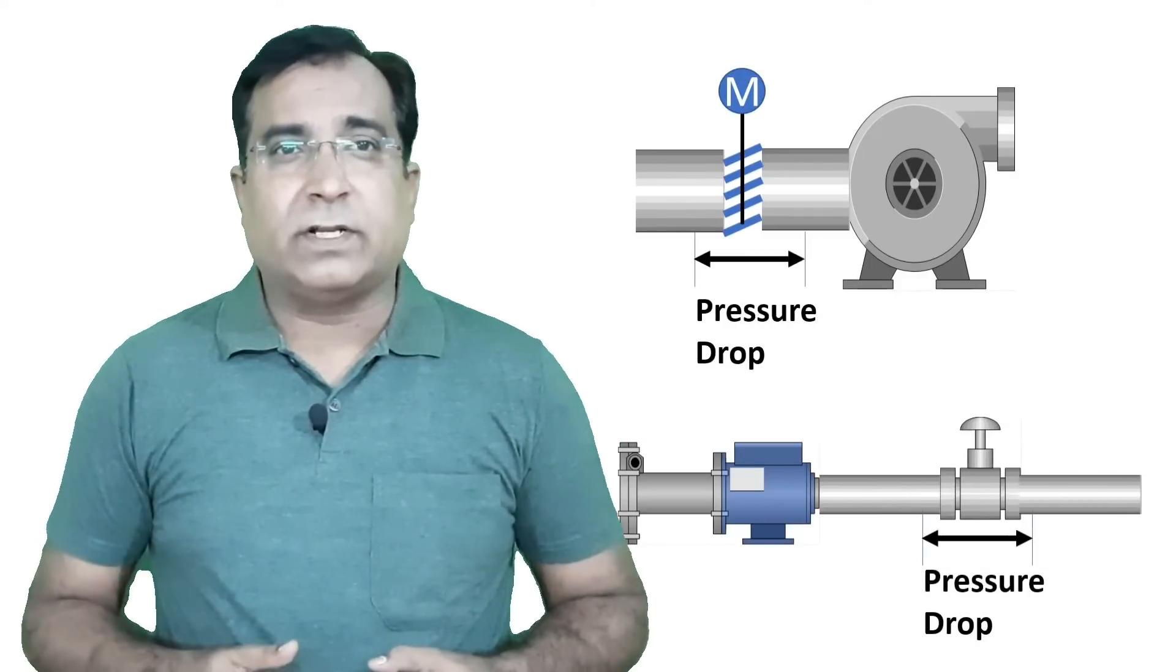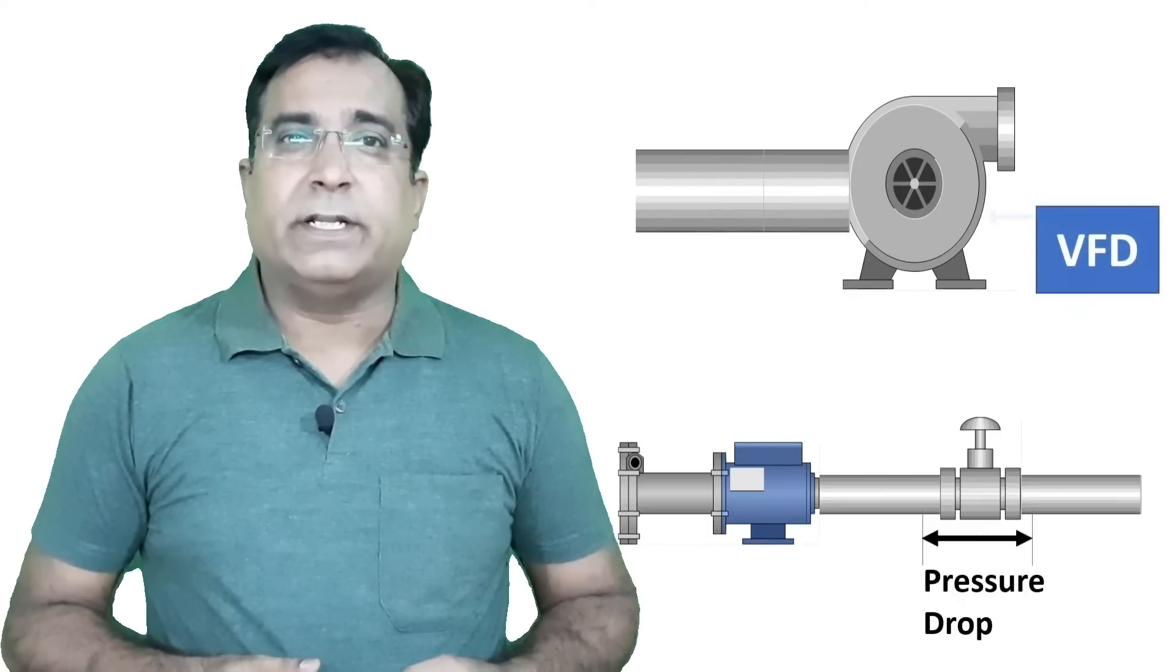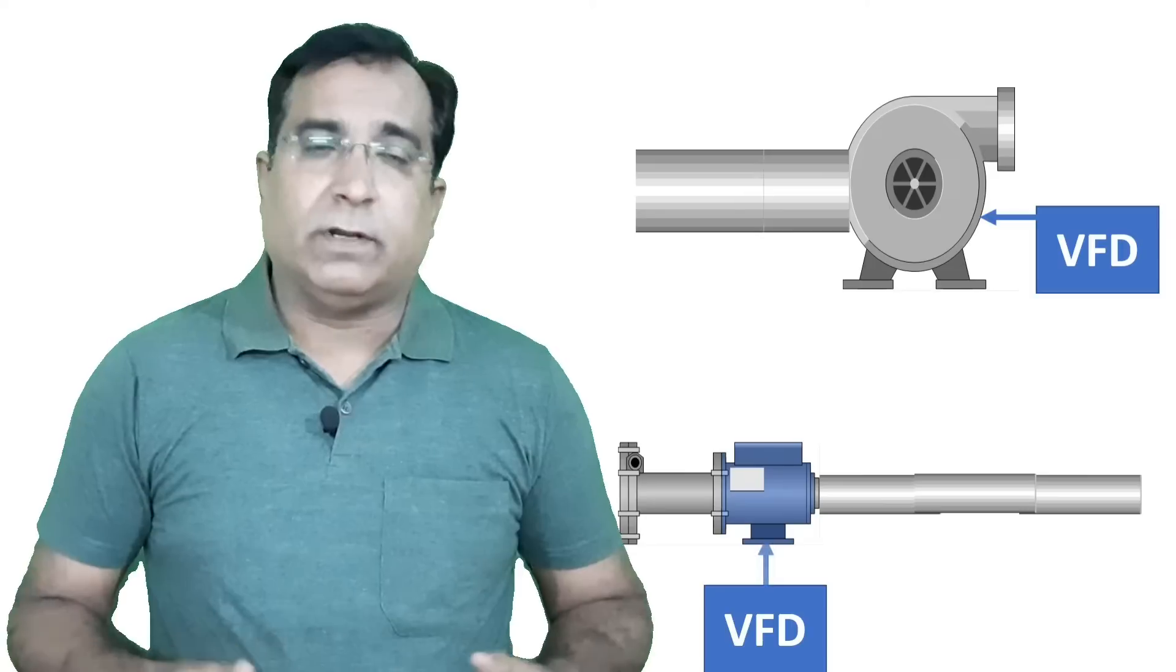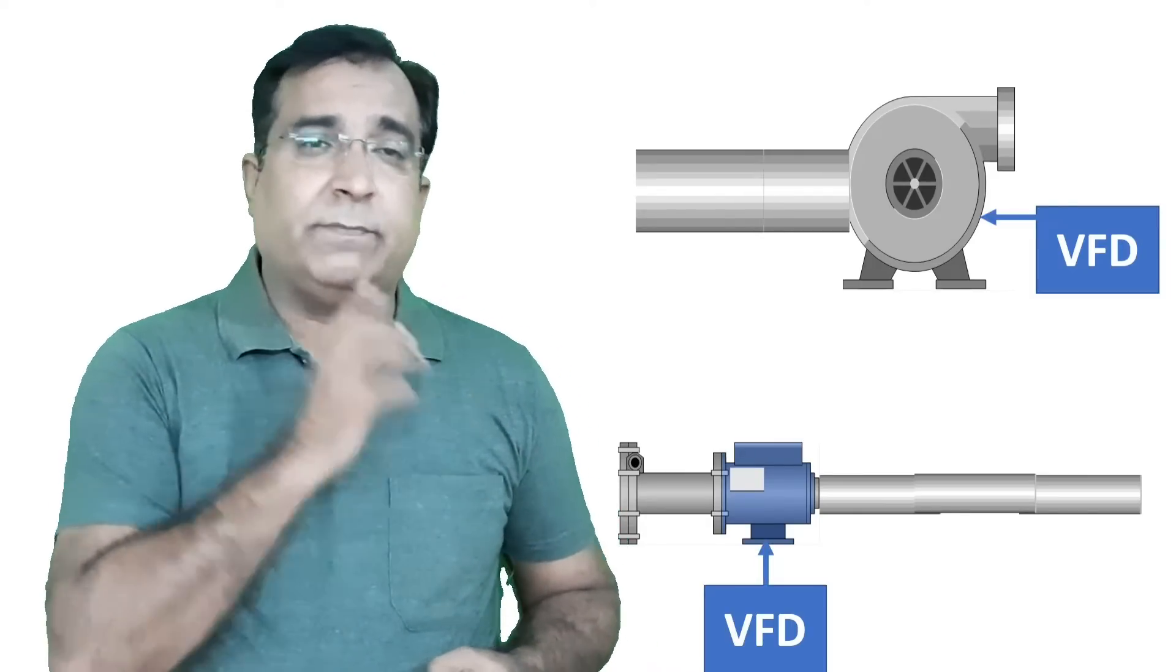Better if these damper and valves are removed and flow is regulated by directly regulating the speed of a fan or pump or blower. A considerable power can be saved, which earlier was being wasted as a pressure drop.